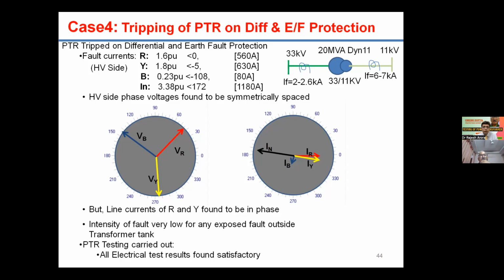I know that if some bus fault occurs outside the transformer, the current is going to be of the order of around 10 to 12 kiloamperes. But I'm just getting 560 ampere currents. So we understood that there is no fault outside the transformer. There must be something within the transformer which is creating a problem.